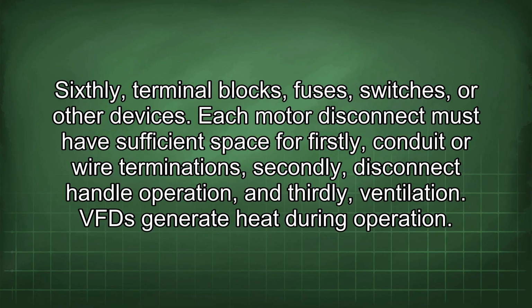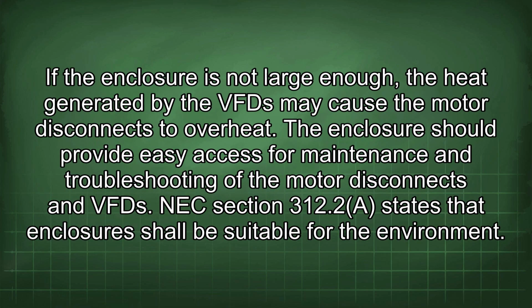Each motor disconnect must have sufficient space for, firstly, conduit or wire terminations, secondly, disconnect handle operation, and thirdly, ventilation. VFDs generate heat during operation. If the enclosure is not large enough, the heat generated by the VFD may cause the motor disconnects to overheat. The enclosure should provide easy access for maintenance and troubleshooting of the motor disconnects and VFD.